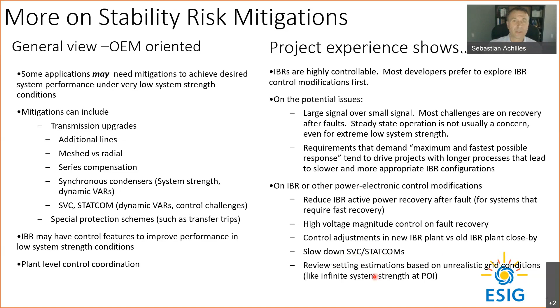So what do OEMs do about weak grid? In principle, when you look at the different controllers in a plant: if you have a solar plant, you'll tend to have a microprocessor that controls the power electronics, and you wouldn't have turbine control. In the case of wind turbines, you will have a turbine control and a converter control at each turbine. And then, independently of the type of IBR, you will normally have a plant controller.